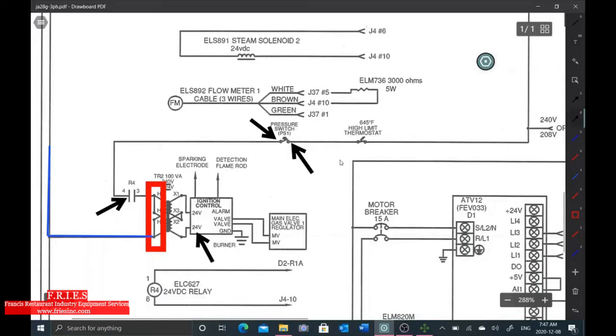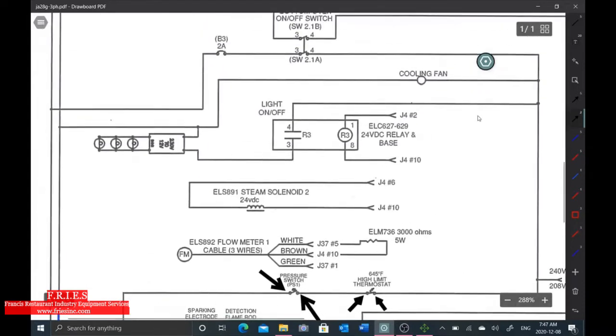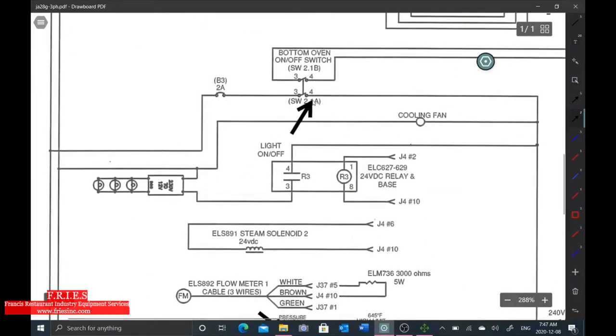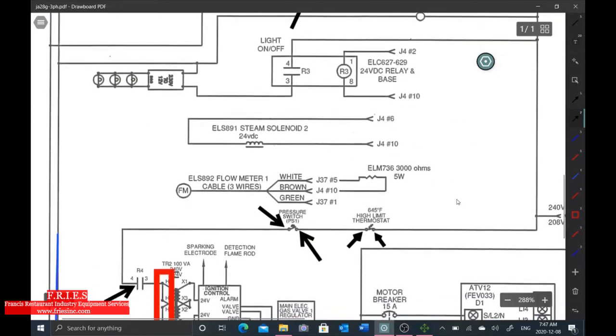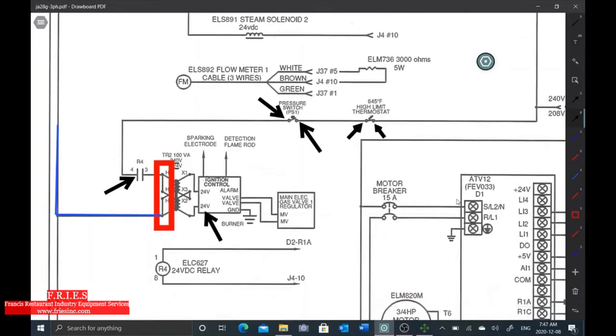My next test point will be that same L2 on the blue line to the thermostat outlet and inlet. If I get 208 right here on the inlet, I know to stop troubleshooting. If I don't, I'm going to keep working backwards, and this comes all the way back up to our switch all the way here. Like I said, because it's an intermittent problem, I have to troubleshoot super quickly, because I've had it where, say I start troubleshooting and 30 seconds later, it starts running again. Whatever switch is open has closed.